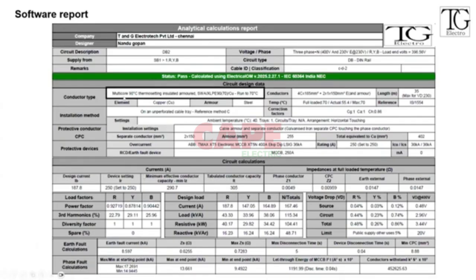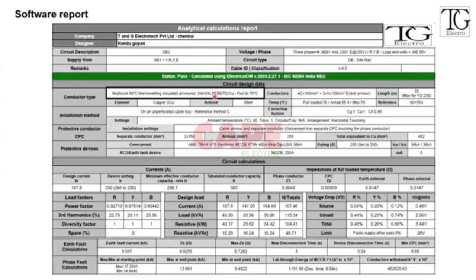What is the conductor size, the cross-sectional area? What is it, XLPE and all those things? Second, is the conductor XLPE or 70 square copper, and whether you are running the conductor at 70 degrees or whether you can run it at 90 degrees, you will be getting this value. You will also get the actual load, the actual current at that value.